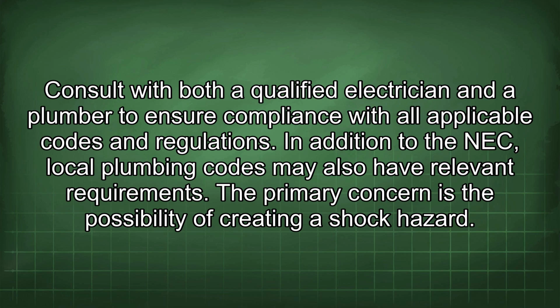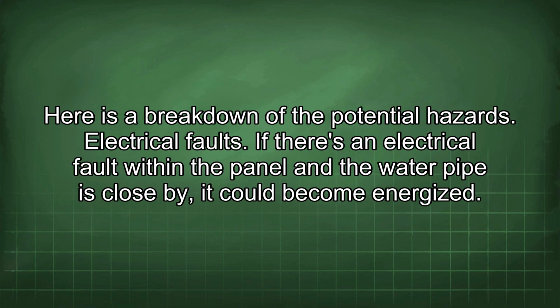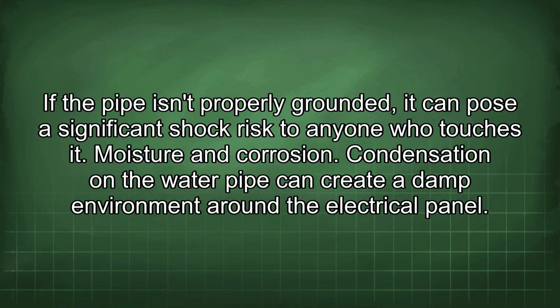In addition to the NEC, local plumbing codes may also have relevant requirements. The primary concern is the possibility of creating a shock hazard. Here's a breakdown of the potential hazards. Electrical faults. If there's an electrical fault within the panel and the water pipe is close by, it could become energized. If the pipe isn't properly grounded, it can pose a significant shock risk to anyone who touches it.